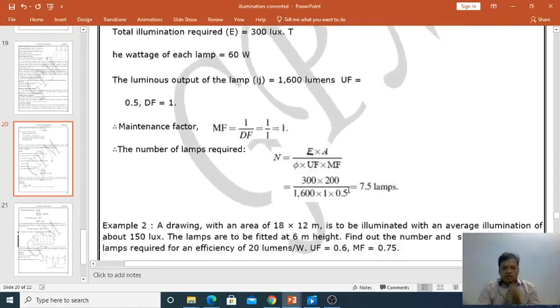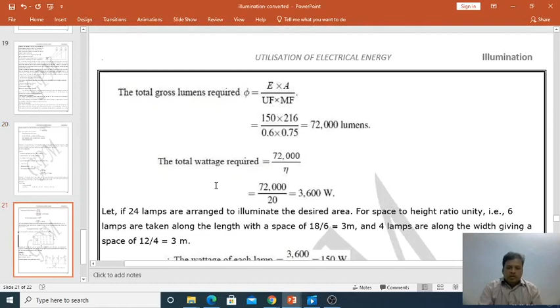This is the second example. A drawing hall with an area of 18 by 12 meters is illuminated with an average illumination of 150 lux. The lamps are to be fitted at 6 meters height. Find out the number and size of incandescent lamps required for an efficiency of 20 lumens per watt. UF is equal to 0.6 and MF is equal to 0.75. Here eta is equal to 20 lumens per watt and E is equal to 150 lux. A is equal to 18 into 12, that is 216 square meters.